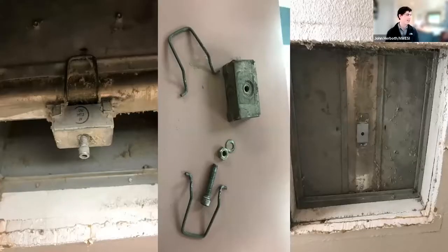This is another one. This is an LC. It's got a 165 temp rating on it, and this is a volume adjustable fusible link. This was on a return duct, and so you can adjust the position of the damper. So it's also a volume damper at the same time as a fusible link. To test it, you can pull it off, but you're going to have to mark the position before you test it.